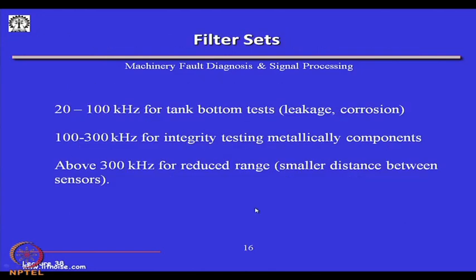Filter sets depend on the acoustic emission application. For leakage and corrosion tests, filters are within 20 to 100 kilohertz. For metallic component testing, filters range from 100 to 300 kilohertz, and above 300 kilohertz for small distances between sensors.